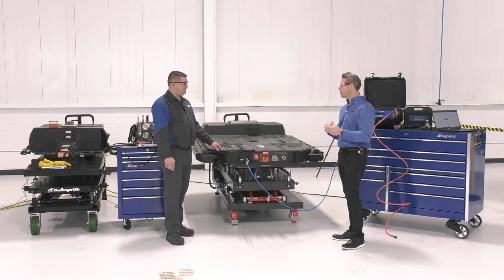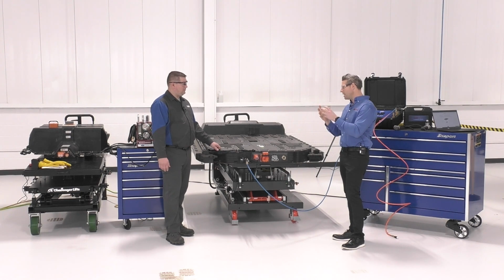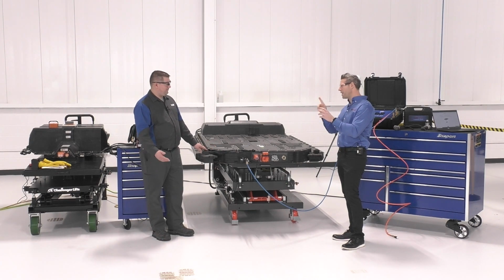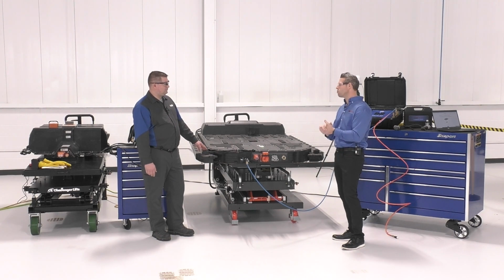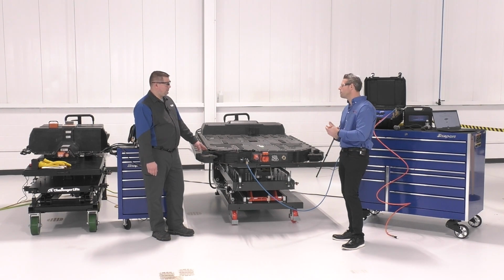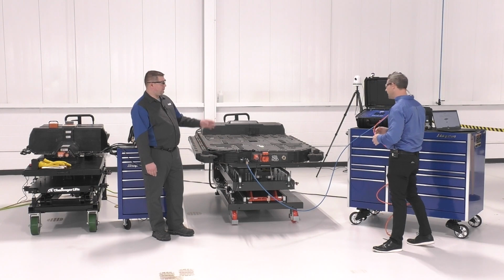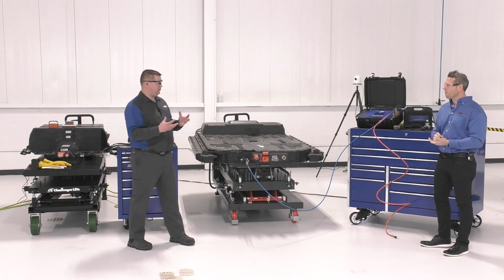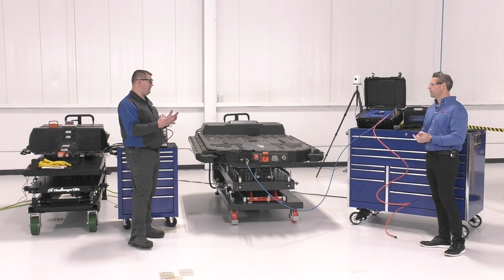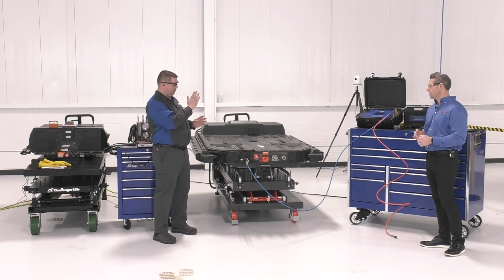Of course, you want to use the recommended equipment, because a bad or less accurate gauge, or one with too large a range, won't let you resolve that kind of pressure drop. One of the cool things about this tool is you actually get good resolution, you can see a clear pressure drop, instead of relying on just a little needle gauge.